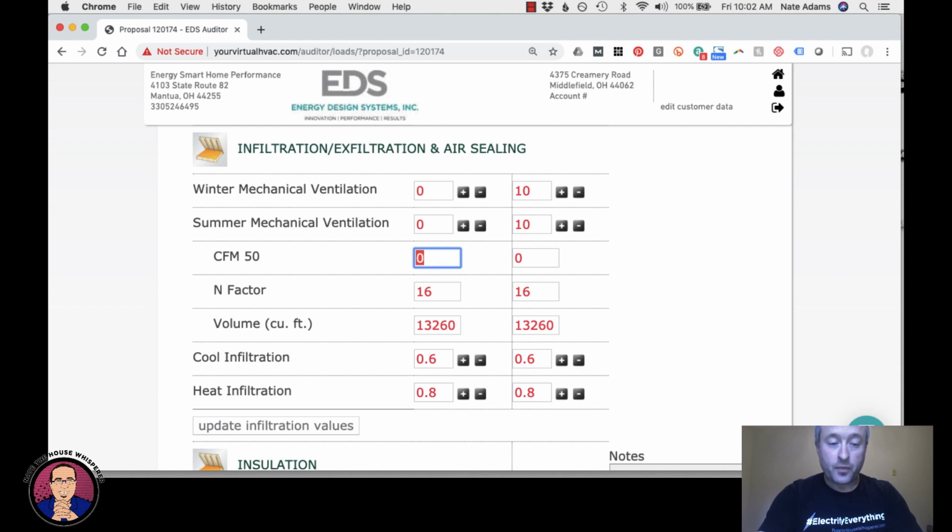So this house, she did a bunch of work to it already. She spray foamed the second floor of the place, and the walls were dense packed. And I actually happened to totally nail my blower door guess on this one. I guessed 2,800. It was 2,800. But the basement of this place is a train wreck presently. That did not get addressed. So that's basically the project is going to look like fixing the basement and changing the HVAC, because the furnace, I have no idea why that thing's still running.